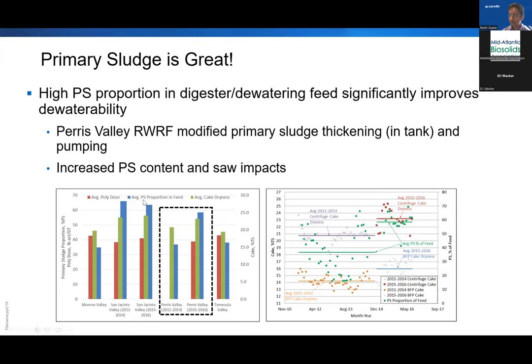And you can see here that the primary sludge proportion went from about 37, 38%. They got it up to almost 58% and they saw this increase in cake dryness. They hadn't been tracking polymer earlier, so we weren't able to track the polymer there. And then this graph on the right showed something similar, where the primary sludge, the green line, jumped from one time to the other. The cake dryness jumped from down here at like 21 up to beyond 23 for the centrifuges. And then similarly for belt filter presses, when they operated the belt filter presses in a standby mode.